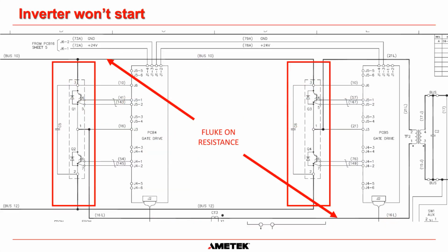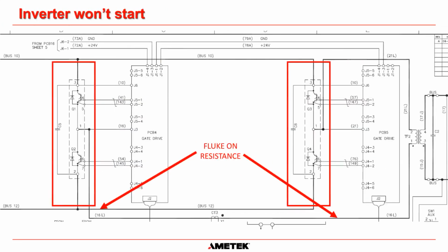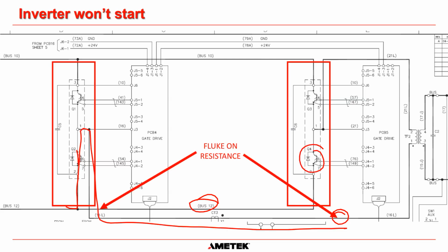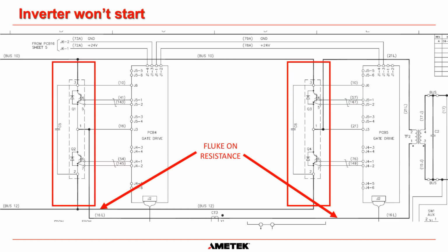And then you just switch your Fluke over to bus 12, keep your other lead on wire 16, and then, let's say Q2 has failed. That will give you a short circuit between there, and the same with Q4. Okay, so that will tell you either this one or this one has failed, or this one and this one failed, with a very easy resistance check using a Fluke.